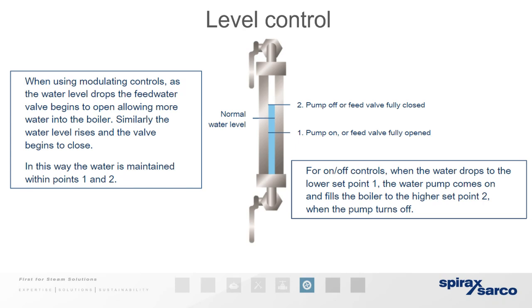However, if the boiler is fitted with modulating pumps, then this is happening at a constant rate. With modulating, you would be maintaining one set position. With on-off control, you would pump up to one level, and then as it drops to a certain point, it would turn on again. So there's a massive difference in the volume of water you're adding to that boiler. When we were talking about thermal shock, this is what we mean. Modulating would hold it at one point, so it's trickling. It's almost like having a leaking tap. On-off is giving a large volume of water into the boiler.